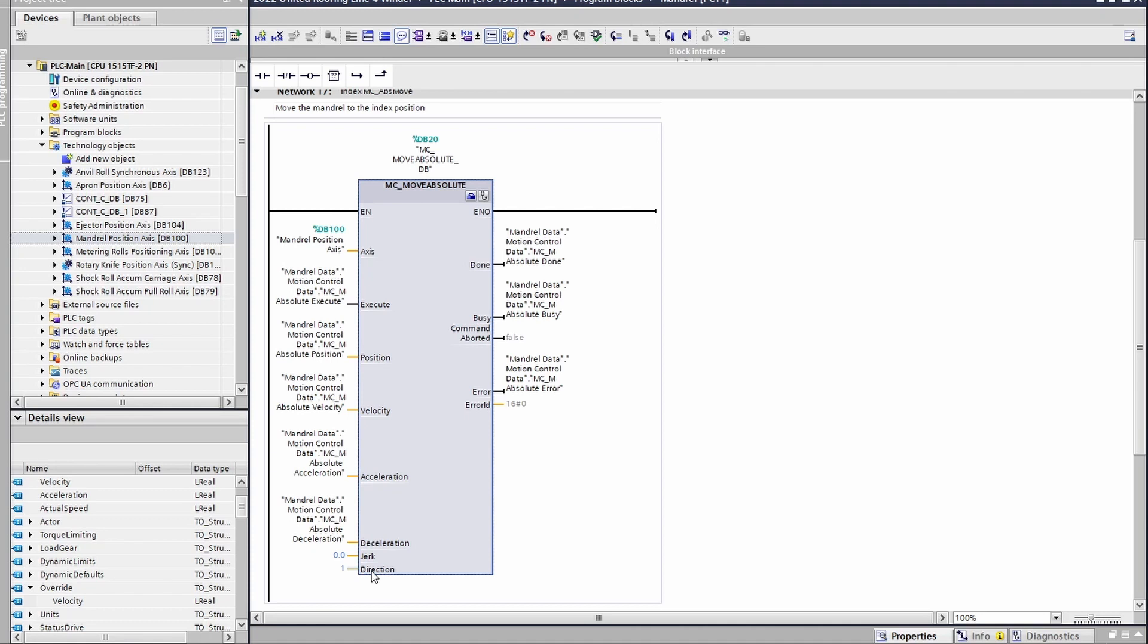As I spoke before about the MC_MoveRelative, a couple of things to look out for if your motion is not executing properly is the velocity, acceleration, and deceleration. If any of those values are zero, then the block won't be able to function correctly. If the velocity is zero, it won't be able to move. If the acceleration is zero, it won't be able to accelerate.